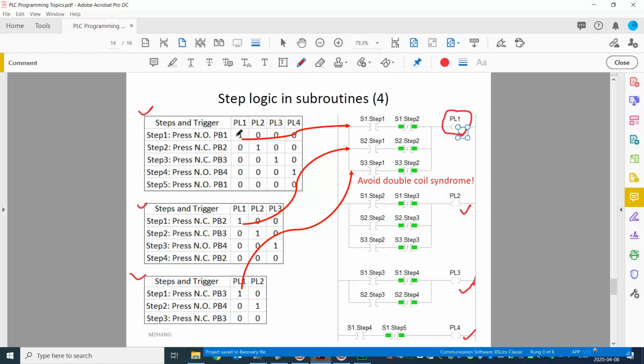Right? In subroutine 1, we energize that from step 1 before step 2. Same thing for subroutine 2 and 3. So that's why you can see that matched to 3 different branches here. Right? So the reason for that you already understand, right? You want to avoid the double coil syndrome.